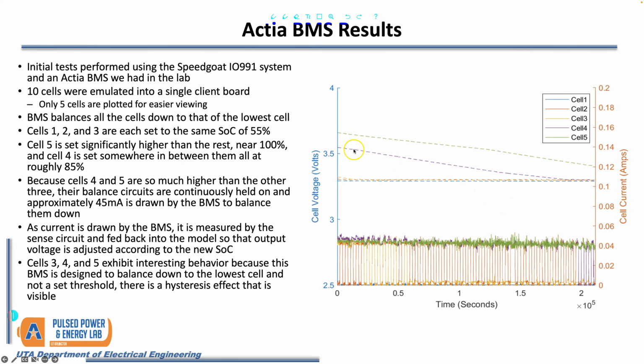Here is the Actia BMS. You can see the cells are out of balance, denoted by cell 4 and cell 5 being above 3.5 volts. The Actia BMS behaves differently than our predicted results: previously the balance threshold was set by a user or programmed in, but on the Actia BMS it balances cells down to the lowest cell voltage, dynamically setting the balance point. So it continues balancing cells 4 and 5 until it reaches that gap.